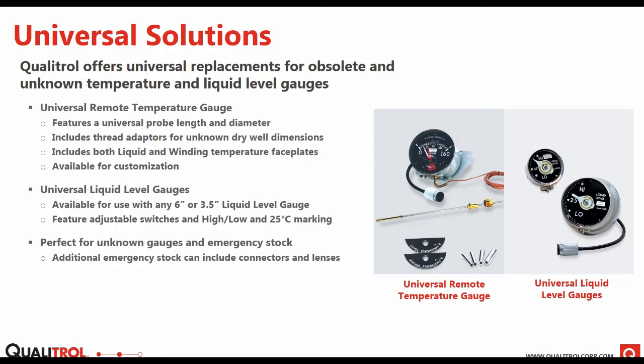Especially when it spends all of its life submerged in oil, there's not a lot of wear on that. Most of them are either a lever design or a gear design, and they're pretty reliable and robust. So most of the time the case, which is out in the environment and the conditions, needs to be replaced. And that's where these universal options will work with any Qualitrol flange from any era, for the most part. It's a quick and easy way to get a replacement in a pinch if you can't go through the speccing process.